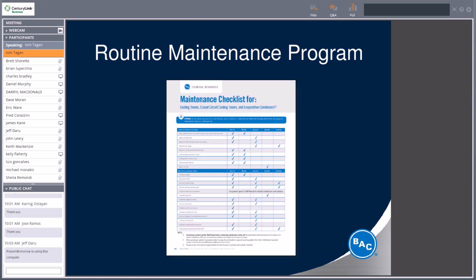If you're up on the roof or wandering around your building, just stop for a moment, and if your tower's running, take a listen, see if everything sounds normal. It also lists inspecting the cold water basin. That's generally for leaks. You want to make sure that the level is not overflowing, and it's also not at a low level. Being at a low level can introduce air into your system and cause pump cavitation and other issues. And again, later on in the presentation, I'm going to show you some specific pages in the O&M for this specific tower that detail the tasks or the maintenance procedures that you need to perform.